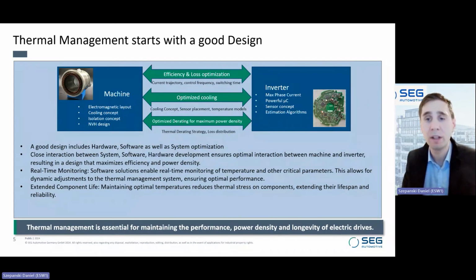That means, on one hand, analyzing how to transfer more heat out of the system, and also identifying critical components and optimizing their placement so that hotspots, which are much hotter than other areas, are avoided. Another important question is where to place the sensor in order to derive a good relationship between the sensor value and the relevant component.